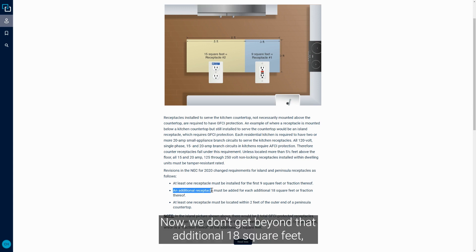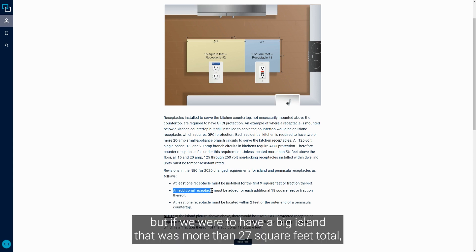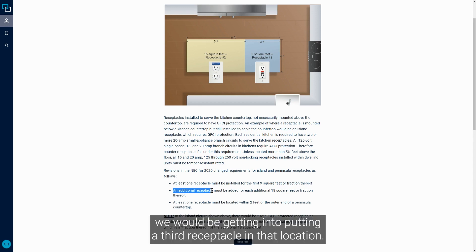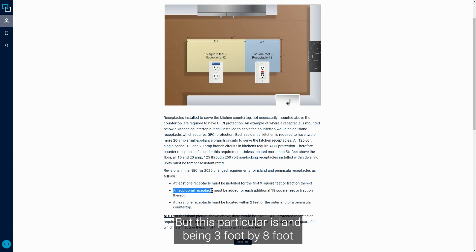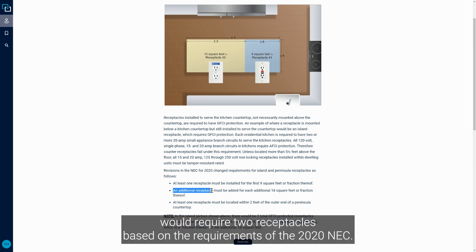Now we don't get beyond that additional 18 square feet, but if we were to have a big island that was more than 27 square feet total, we would be getting into putting a third receptacle in that location. But this particular island being three foot by eight foot would require two receptacles based on the requirements of the 2020 NEC.